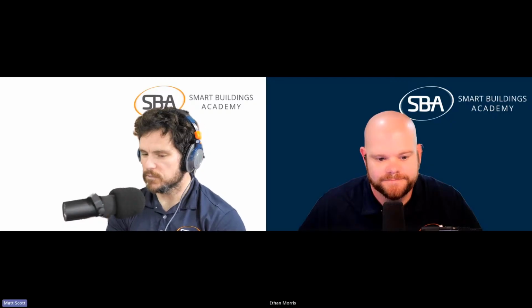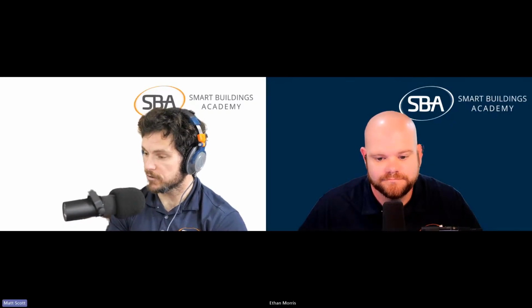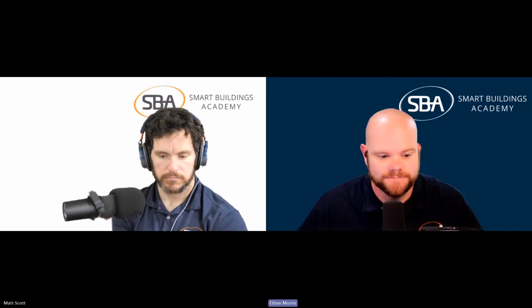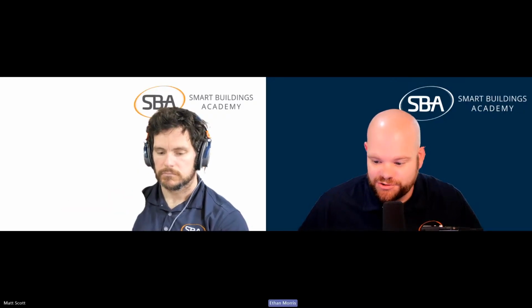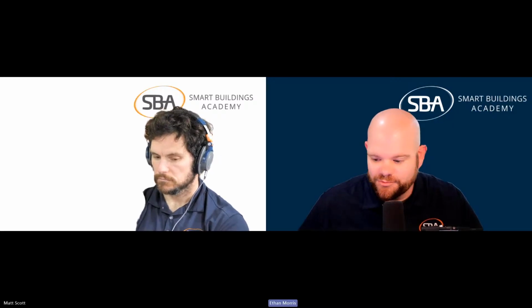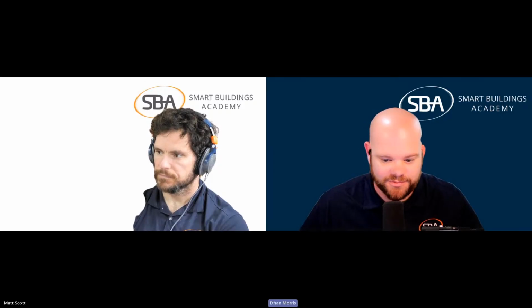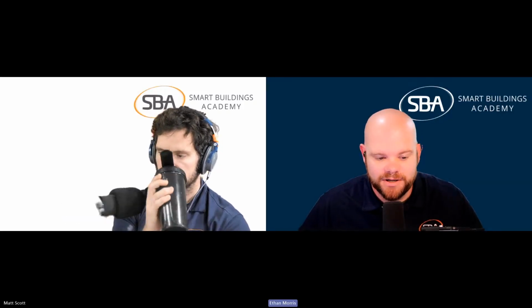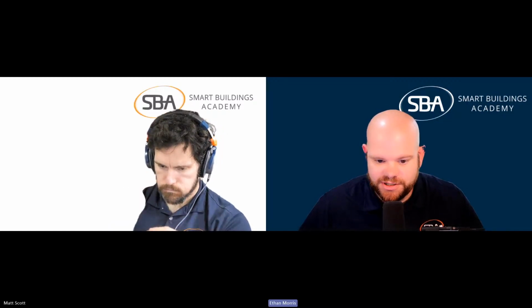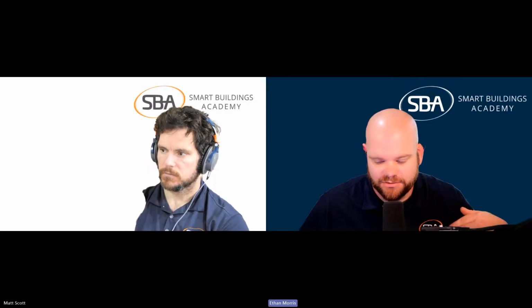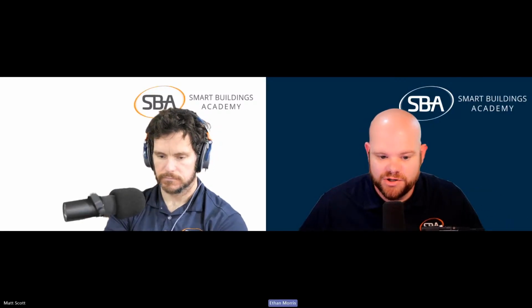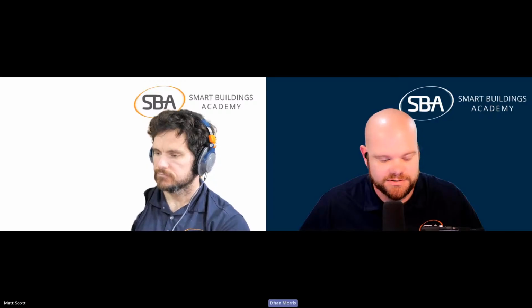Can you explain the difference between heat pump and heat recovery in VRF systems? Sure. Typically nowadays you find more heat recovery systems than anything because it allows for individual zoning control. You could have 30 rooms in a building. If you have 30 branch selector boxes with those 30 units, each room can control its own heat, its own cool, and it can be different from any of the other rooms in that hallway. A heat pump system in a VRF will still use an inverter compressor, so you still have that ramp up and down of compressor speed. But the difference is that all the zones are either going to be in a heating or cooling mode together. You're not going to have that individual zoning like you would with a 3-pipe heat recovery system.